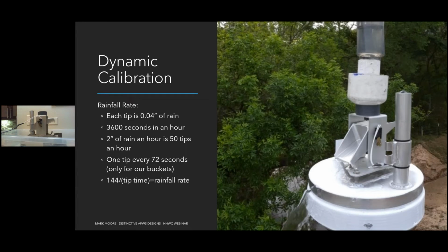During a dynamic calibration, we know that the rainfall rate can be determined based off of the type of bucket you've got. And I didn't do the math here because I've done it before with these tipping buckets. These are High Sierra 1 millimeter tipping buckets that we're using in this example. Each tip is 1 millimeter of rain or 0.04 inches of rain. And if you do the math, there's 3,600 seconds in an hour. So 2 inches of rain an hour would be 50 tips an hour, which ends up being 1 tip every 72 seconds. And that only applies for the buckets we're talking about today. That only applies for a 12-inch diameter collection funnel that's measuring 0.04 inches of rain per tip. But what we can actually do is take 144 divided by the tip time and get the rainfall rate from that.